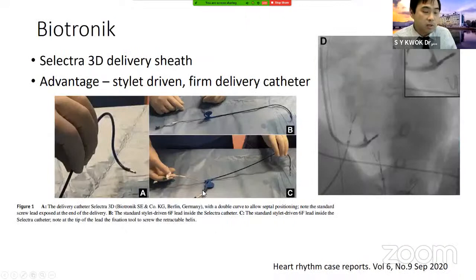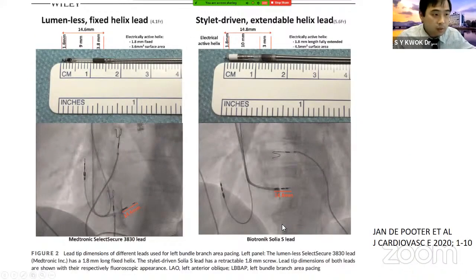The other system that you can use is the Biotronik one, which has a firmer delivery sheath catheter, and also the advantage that it is stylet driven. So the stylet can guide the catheter towards the site that you want to go. Of course, for the two leads, the profile is almost similar, and the length of the helix, the ring and the capture electrode is similar, though the lead for the Biotronik one is a little bit larger in size.